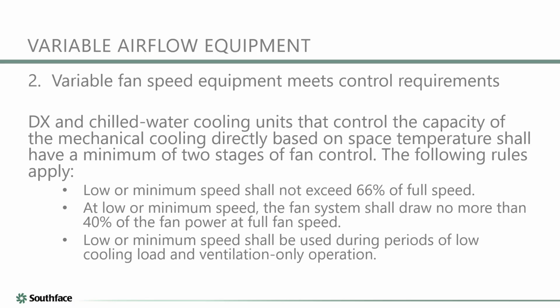It also says that your fan can't use more than 40% of the power at low speed than it would draw at full speed. So again, a limitation around the speed of the fan and the power draw of the fan motor. Again, this is essentially just a way of making sure that if you're saying we have variable speed equipment, it really does function with a lower fan draw and a lower fan speed. The benefits to this are being able to better match the load on spaces, better dehumidification when you move air across a coil more slowly, and lower energy use when you have an adjustable fan speed.